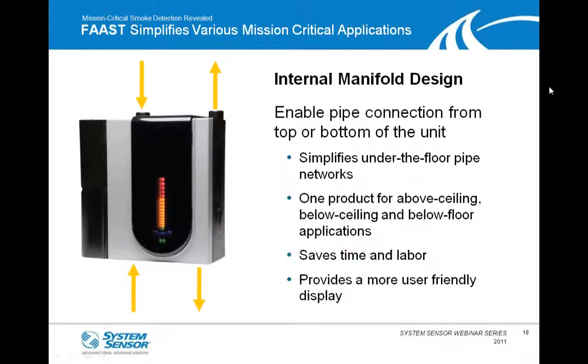So what does FAAST have that can help meet that need of potentially having to have detection below the floor and above the ceiling? Well, FAAST actually has an internal manifold, and what that does is it enables pipe connections from the top of the unit or the bottom of the unit. So it simplifies underfloor pipe networks. Many of the competitive products require that the unit be installed inverted or upside down if you need to bring piping in from the floor or from the bottom of the unit.